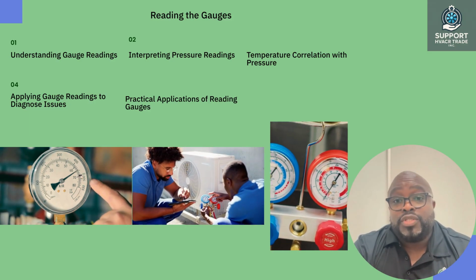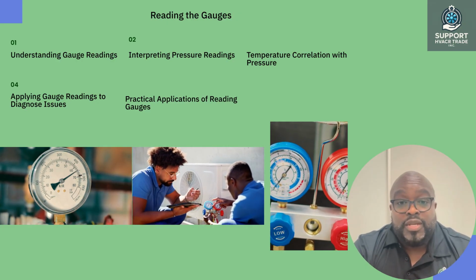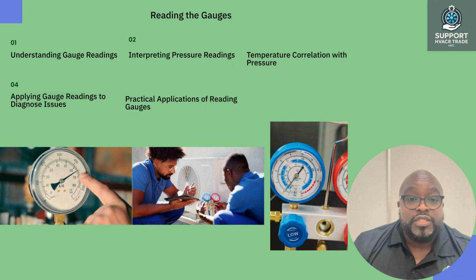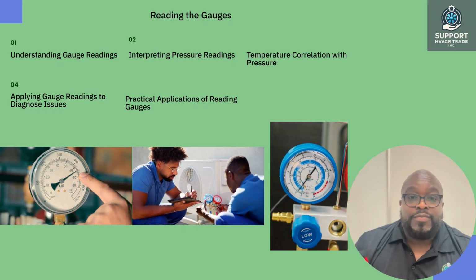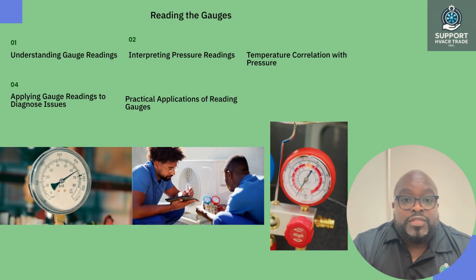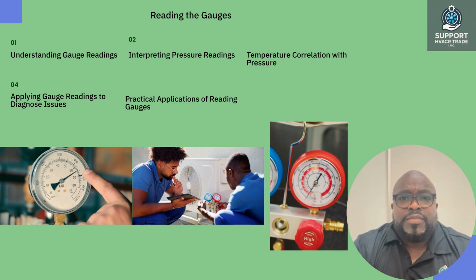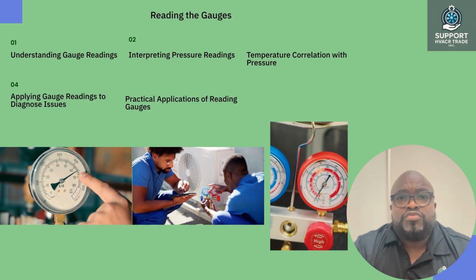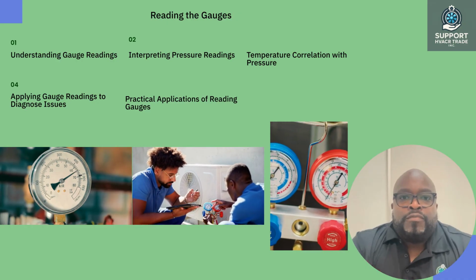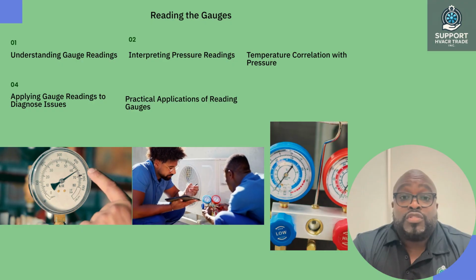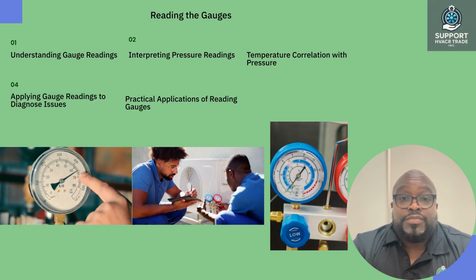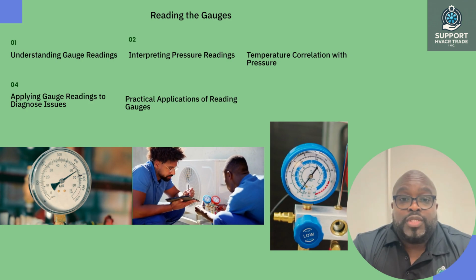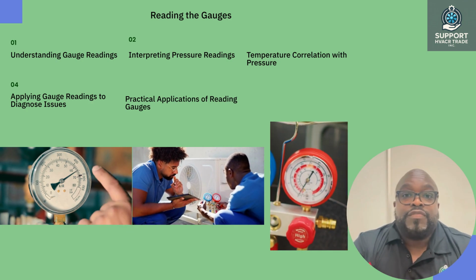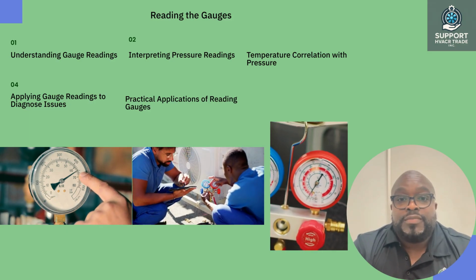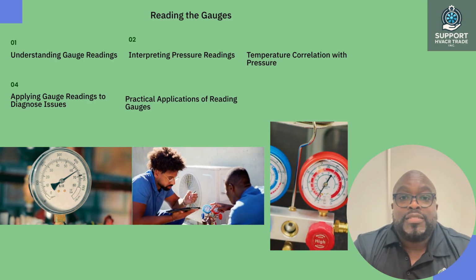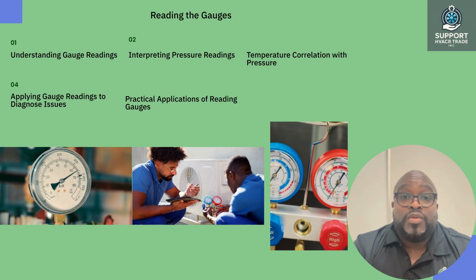Temperature correlation with pressure. Understanding the relationship between temperature and pressure is vital. The pressure readings on the gauges can be cross-referenced with temperature data to achieve a more accurate diagnosis. This relationship is defined by the principles of thermodynamics, where pressure increases with temperature in a closed system. For instance, if you are working with R410A refrigerant, knowing the saturation temperature at which the refrigerant boils at different pressures can help you determine if the system is functioning correctly. Use a pressure-temperature chart specific to the refrigerant to make these assessments. Applying gauge readings to diagnose issues.